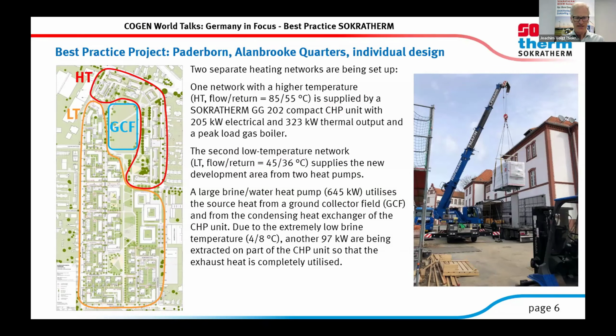And this is a very interesting aspect because we serve the condensing heat exchanger with extremely low temperatures, 4 degrees inlet temperature, 8 degrees outlet temperature. So another close to 100 kilowatt thermal power is being extracted from the CHP unit, so that the exhaust heat of the CHP is completely utilized and multiplied, of course, by the COP of the heat pump.